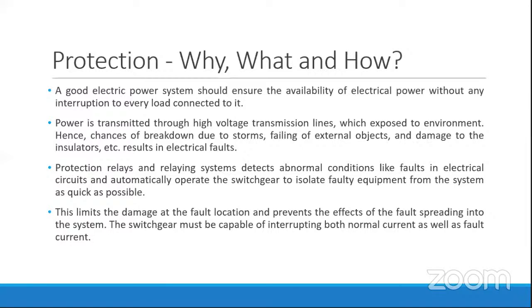So in order to safeguard the entire system and to maintain the continuity of the supply, we need to install protection schemes to save the healthy system from getting damaged by the fault, and to minimize the damage to the equipment and the repair cost. Even by installing these electric relays, or by giving protection to the system, we can minimize the damage, and it will also save our equipment, and consequently we can say it saves our cost. The protection is also applied to give safety to the person who is nearby the equipment.